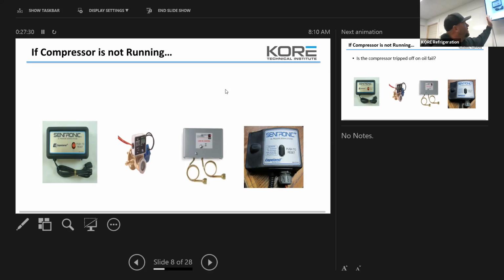Okay, that controller, these two, this is an old style of Sentronic. This is a newer style. Now they have CoreSense, which is an even newer style of controller that actually senses a lot more on the compressor. But any of these are all oil fail controls. So this is an OMB module or a Trax oil, depending on the technician you talk to. They're going to call it two different things. OMB is the model number. Trax oil is what it used to be called, but it's the same type of controller.